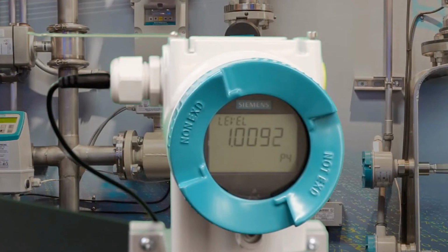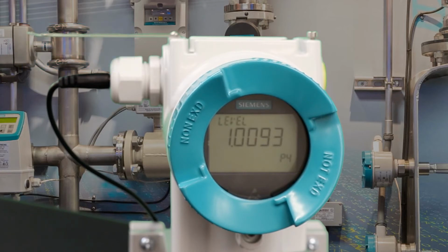Our third application is for a liquid with a specific gravity different from water. In that case, specific gravity is 0.9. So the pressure exerted on the transmitter when the tank is full is 20 feet times 0.9, which is 18 feet of water. Now, what we need to do is scale the pressure transmitter to read from 0 to 18 feet of water. And obviously, as we know, the display needs to show from 0 to 20.